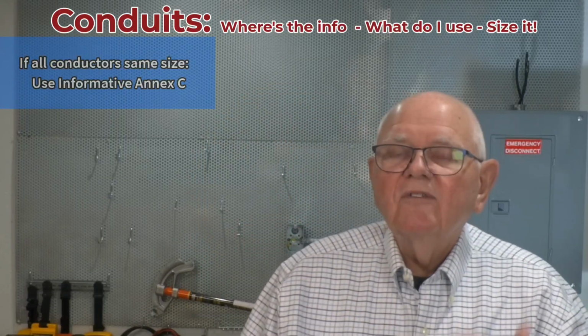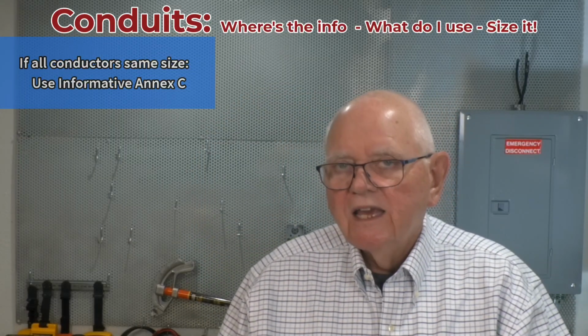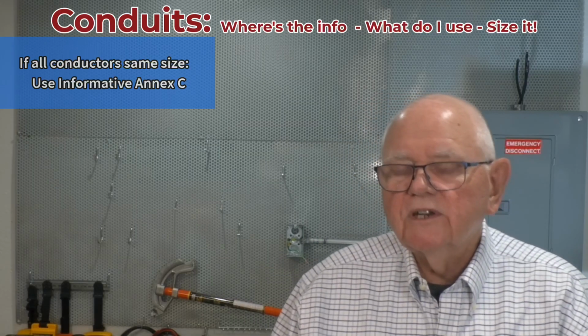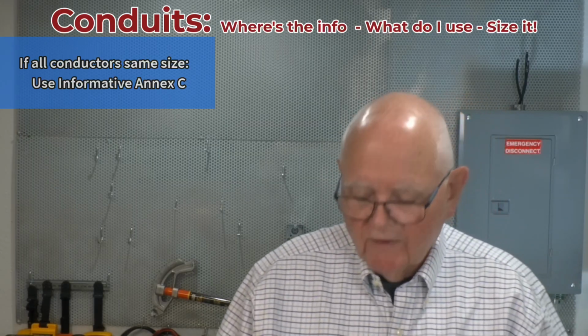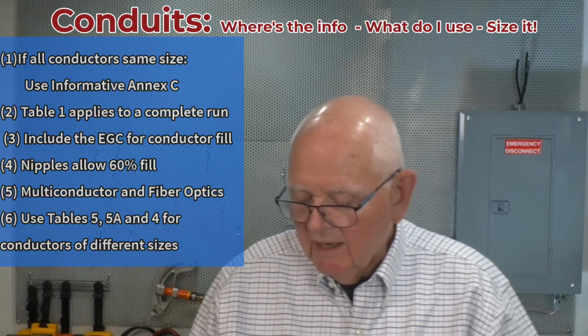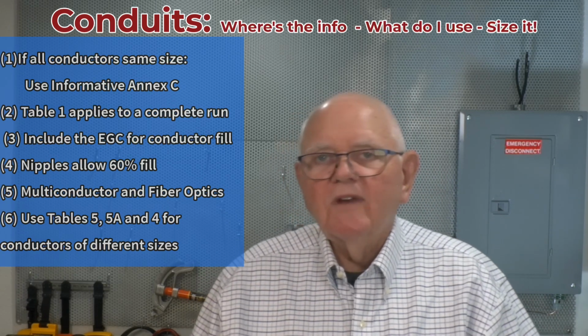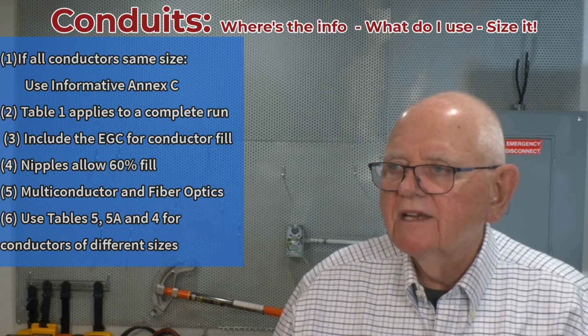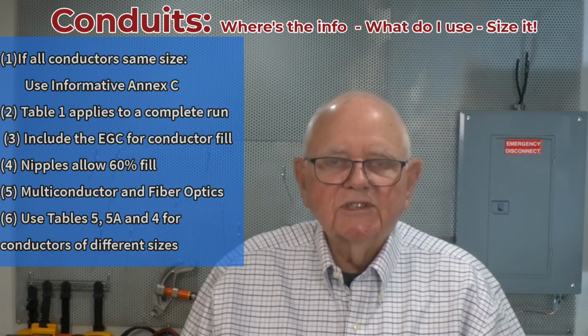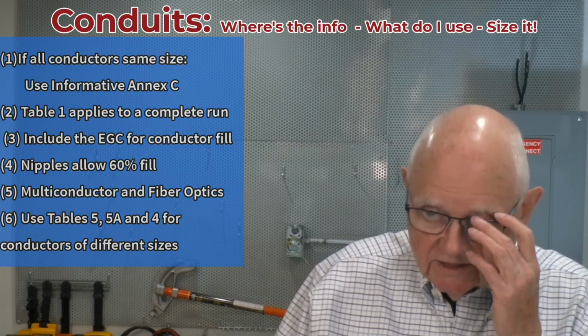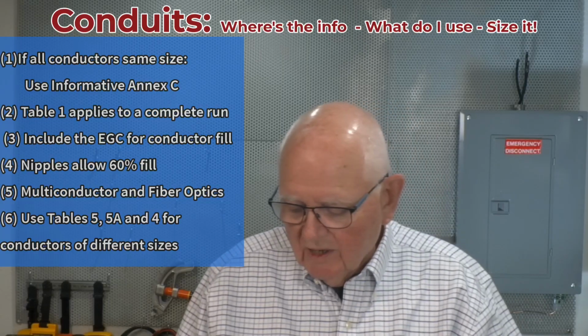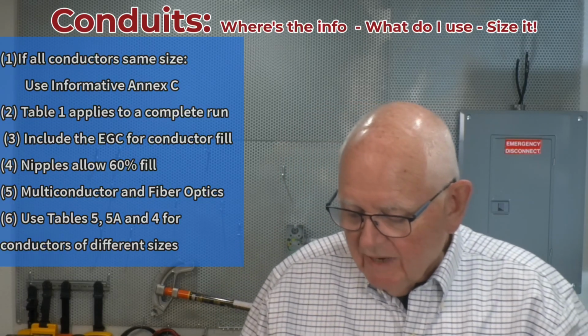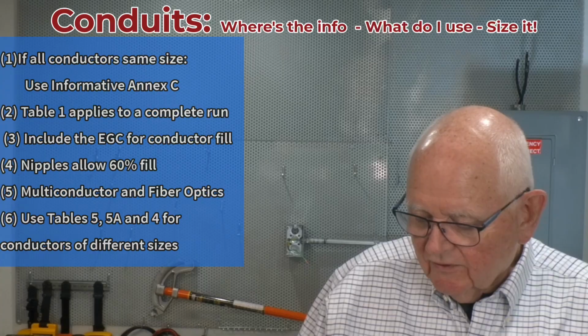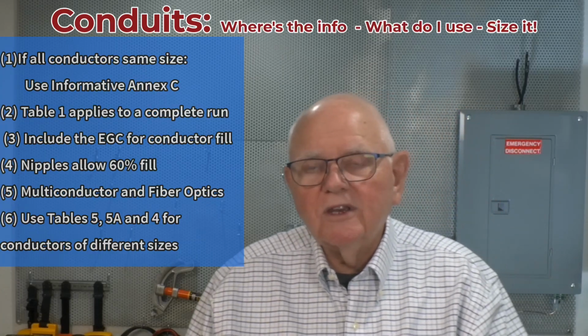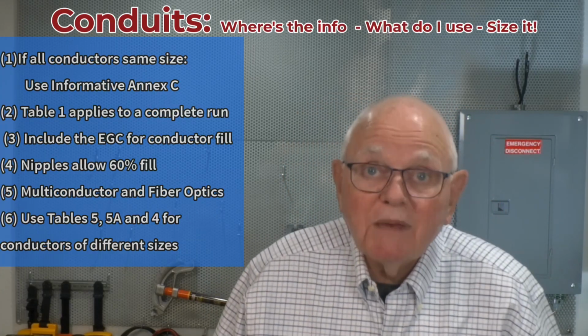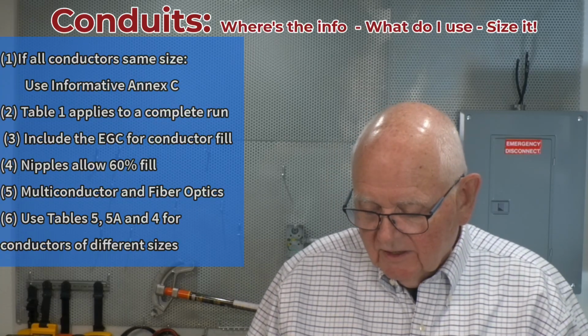Note number 1, if all my conductors are the same size, and how many conductors can I put in that raceway? It says go to Informative Annex C. Table 1 applies to a complete conduit run. It doesn't apply if I'm just using a short run of raceway for some reason to give some physical protection to conductors. My fill requirements don't apply. Equipment grounding and bonding conductors, note number 3, shall be included when calculating my conductor fill. They take up space, so I have to include them in my calculation.